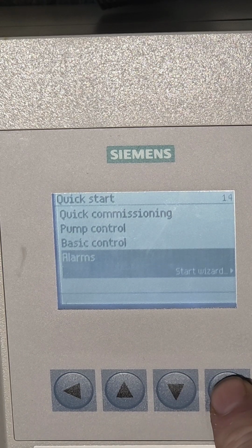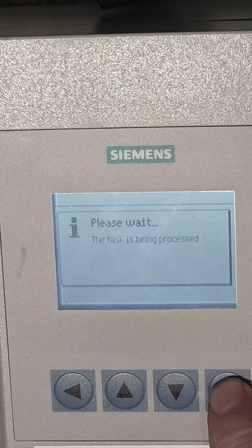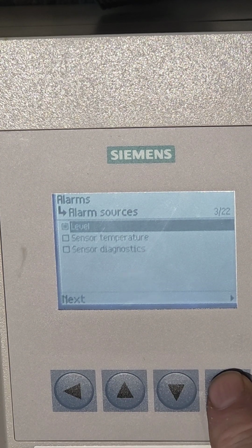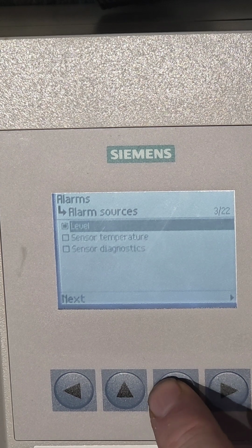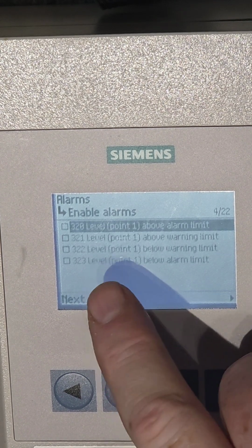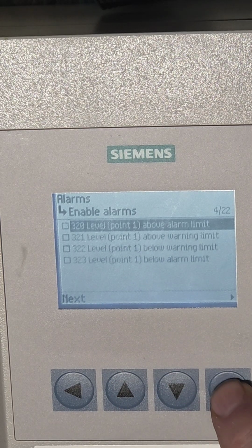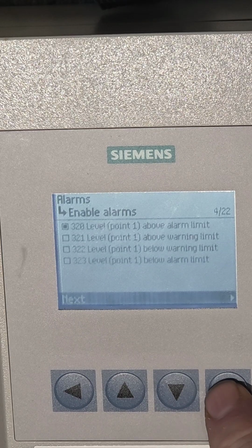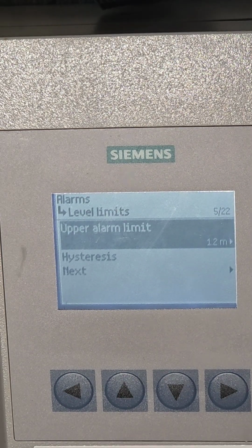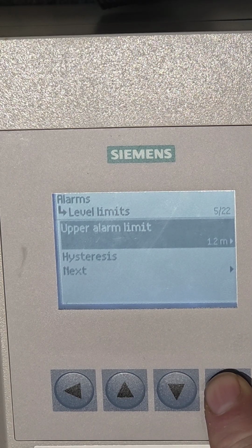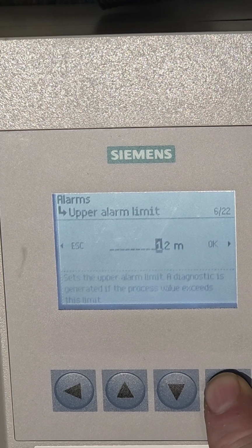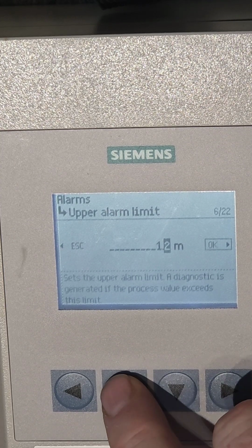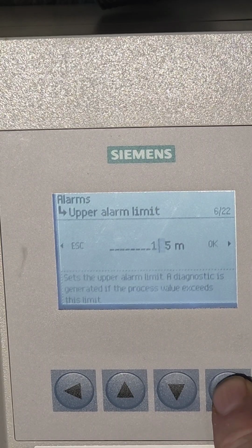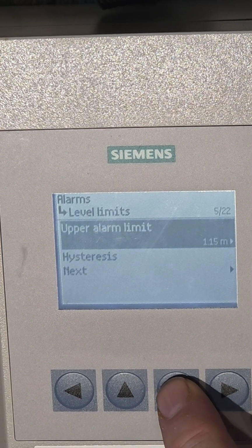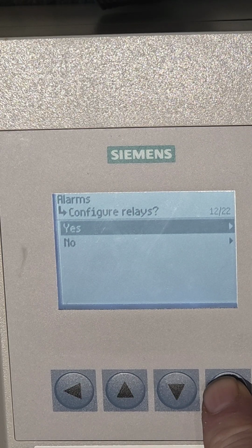Now we come down to set the high level alarm on relay 6. Set it for level. Next. We highlight level above alarm limit. Next. So I want it to be 1.15. And OK. Next. Do you want to configure relays? Yes.